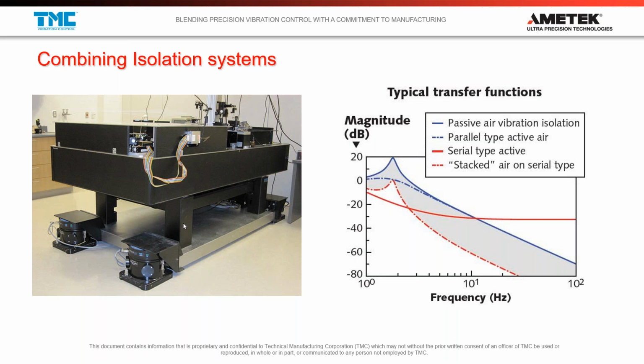So if I now inflate these isolators, so I've got inflated isolators on this floor platform, I have a little bit of a trade-off because I have to deal with that resonance coming back into the system. So adding on to this curve, I have the resonance, but then I have the isolation of those isolators. So again, I have a nicely combined system, but then I have this resonance that I'm dealing with. Well, that was the sort of first step of this.